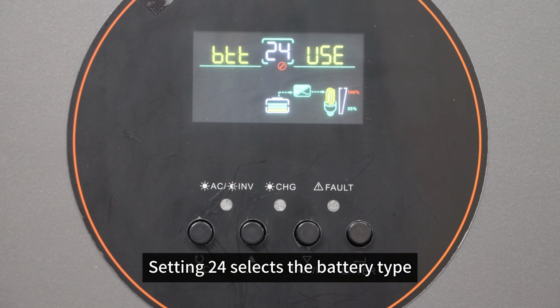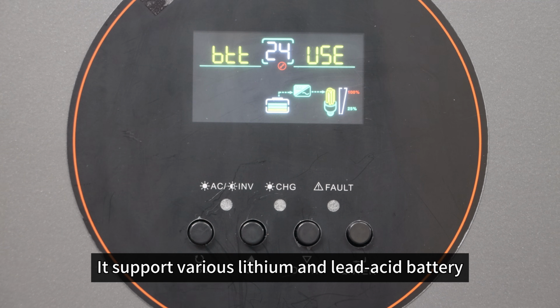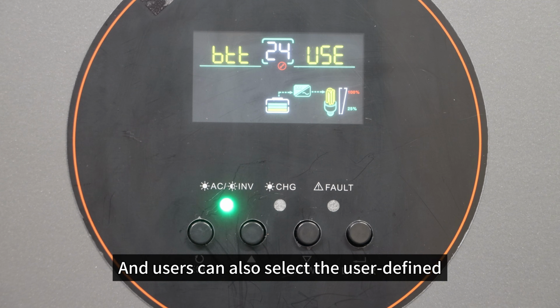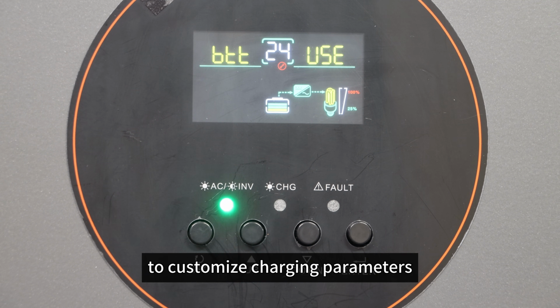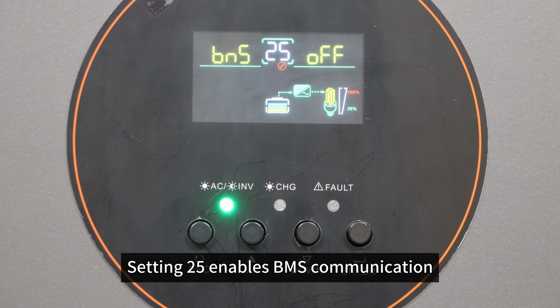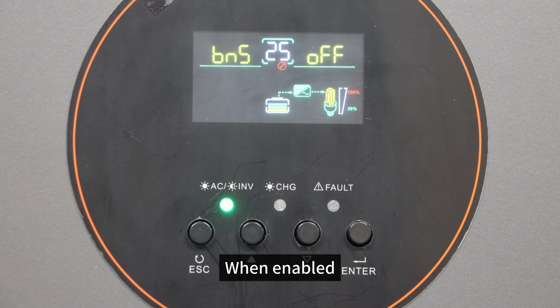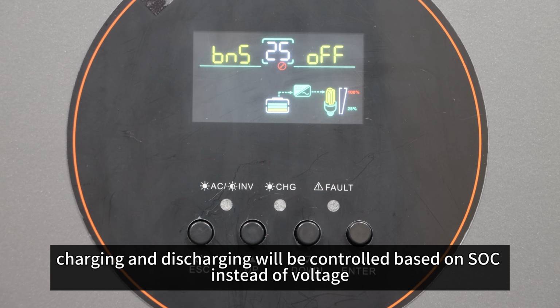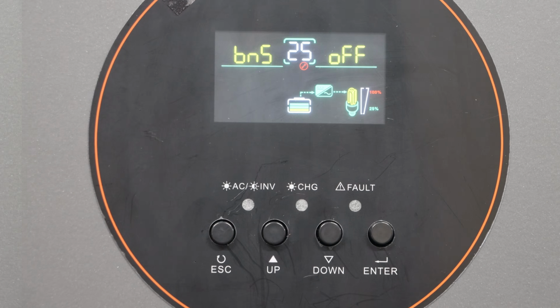Setting 24 selects the battery type. It supports various lithium and lead-acid batteries, and users can also select user-defined to customize the charging parameters. Setting 25 enables BMS communication. When enabled, charging and discharging will be controlled based on SOC instead of voltage.